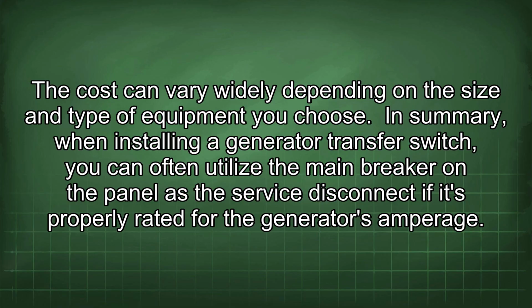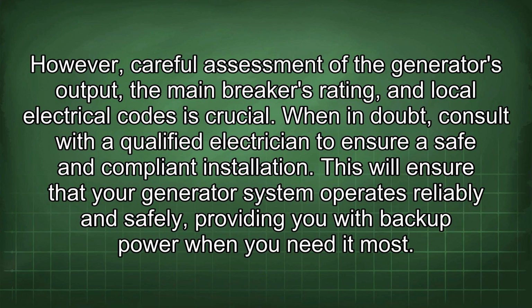In summary, when installing a generator transfer switch, you can often utilize the main breaker on the panel as the service disconnect if it's properly rated for the generator's amperage. However, careful assessment of the generator's output, the main breaker's rating, and local electrical codes is crucial. When in doubt, consult with a qualified electrician to ensure a safe and compliant installation. This will ensure that your generator system operates reliably and safely, providing you with backup power when you need it most.